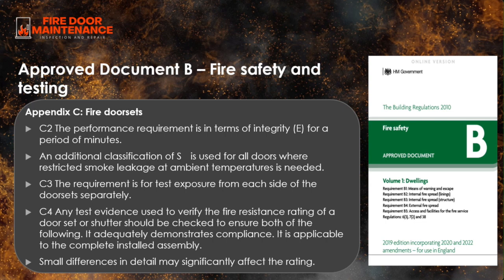The term integrity relates to how long the fire door set should stay intact without breaking down or the fire burning through it. If the location of the door set requires it to hold back smoke as well, this is noted with the addition of S in the classification requirements in that table. In item C3 of the approved document, there is now a specific mention that the door needs to be tested from both sides, and not just on one side as they had been done previously.